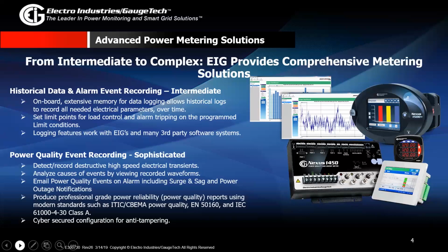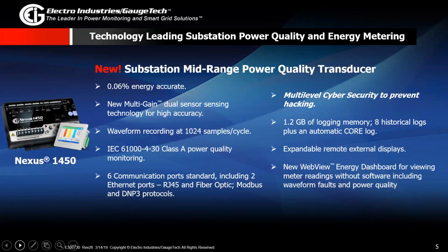The main two meters that I'm going to be talking about are the Nexus 1450 and the Nexus 1500 Plus, which are our newer Nexus generation meters. The Nexus 1450 is a mid-range power quality transducer. It's up to 0.06% energy accurate. And it's not just that it's very accurate, but it will also maintain its accuracy over low loads as well as high loads, because this meter has technology inside it called multi-gain dual sensor technology. Now, what do I mean by that? This meter has two circuits inside it. One circuit is used for sensing when you have low loads, so your current is in the milliamp range.